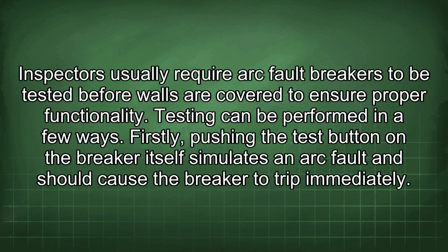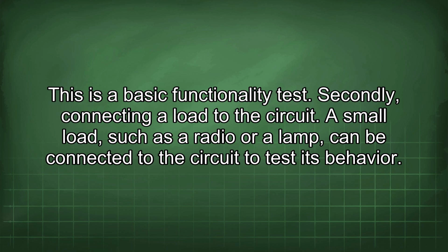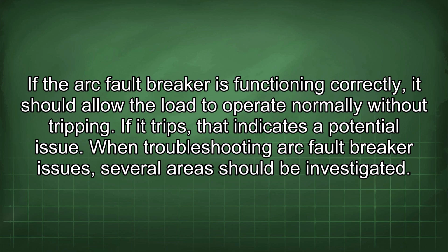Testing can be performed in a few ways. Firstly, pushing the test button on the breaker itself simulates an arc fault and should cause the breaker to trip immediately. This is a basic functionality test. Secondly, connecting a load to the circuit. A small load, such as a radio or a lamp, can be connected to the circuit to test its behavior. If the arc fault breaker is functioning correctly, it should allow the load to operate normally without tripping. If it trips, that indicates a potential issue.